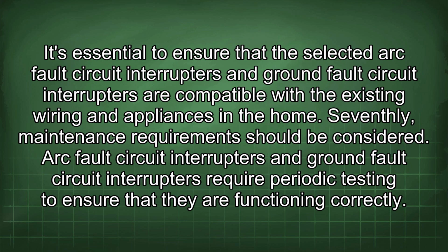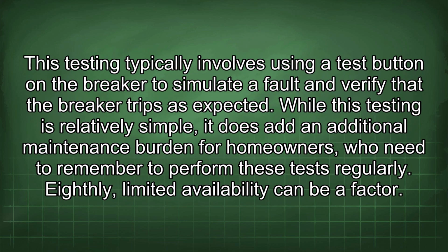Seventhly, maintenance requirements should be considered. Arc fault circuit interrupters and ground fault circuit interrupters require periodic testing to ensure that they are functioning correctly. This testing typically involves using a test button on the breaker to simulate a fault and verify that the breaker trips as expected. While this testing is relatively simple, it does add an additional maintenance burden for homeowners who need to remember to perform these tests regularly.